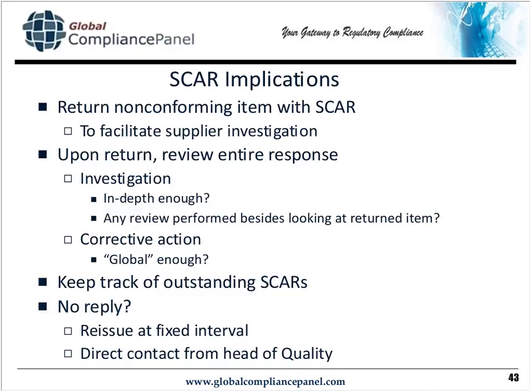As I mentioned earlier, you do want to try to return the nonconforming item with the SCAR. It helps the supplier out. When the SCAR is returned, look at the investigation. Make sure that your originator and quality look at it to make sure the investigation is in-depth enough. And did they do anything other than looking at the returned item? We do see that from time to time. Just want to give you a heads up on that. And when it comes to corrective action, ask yourself whether the corrective action was what I call global enough. Was it truly corrective enough, or was it merely just a correction to the part?